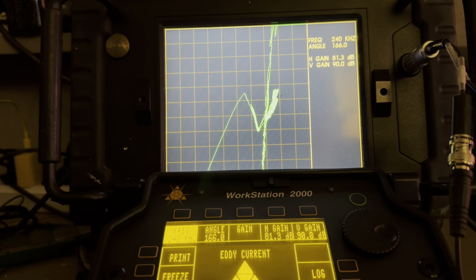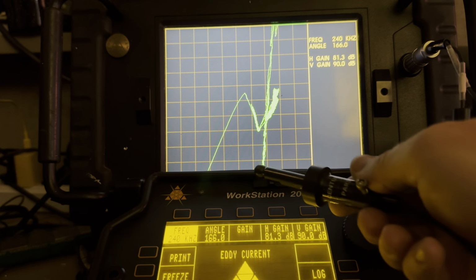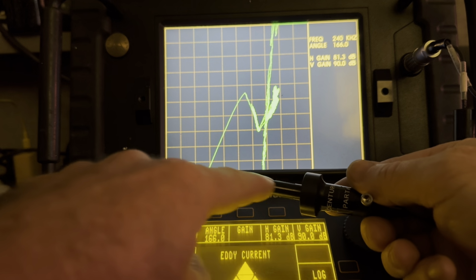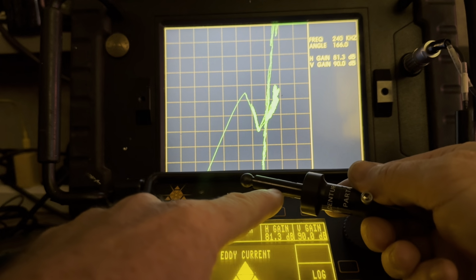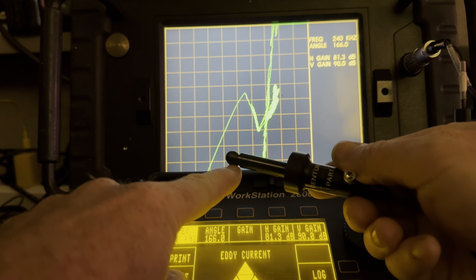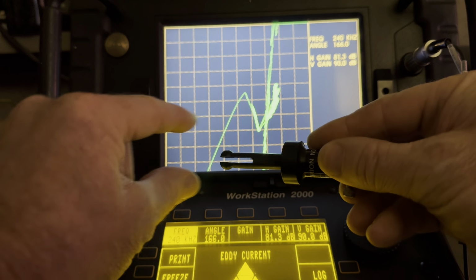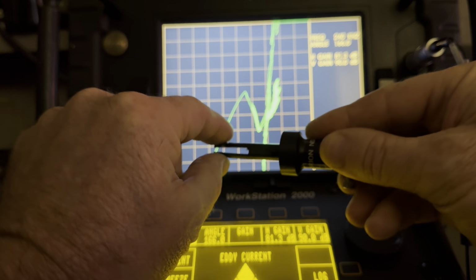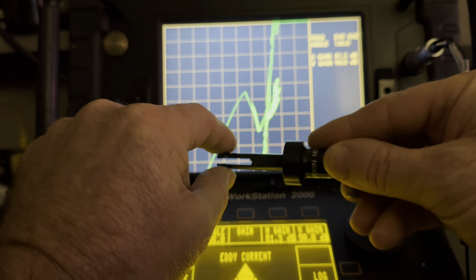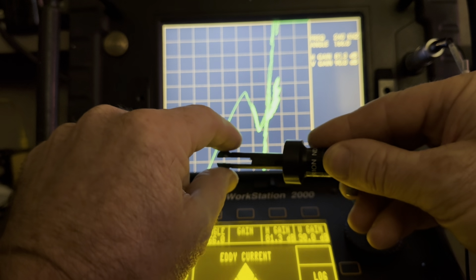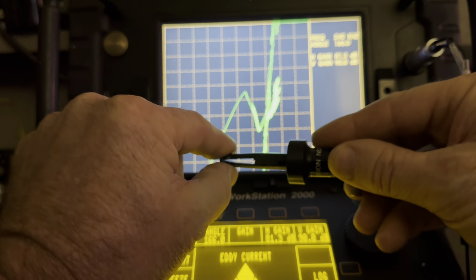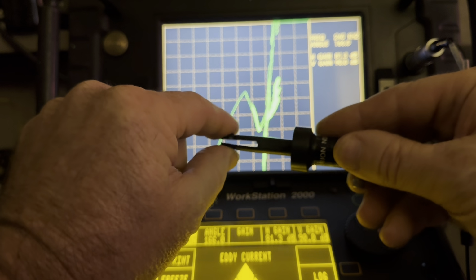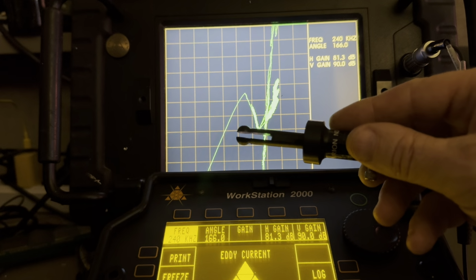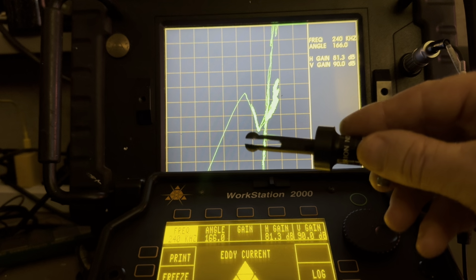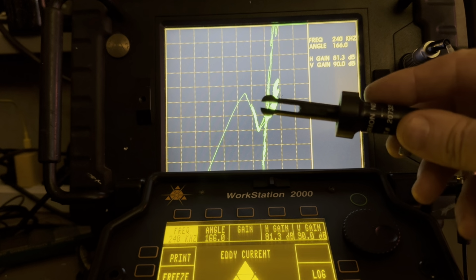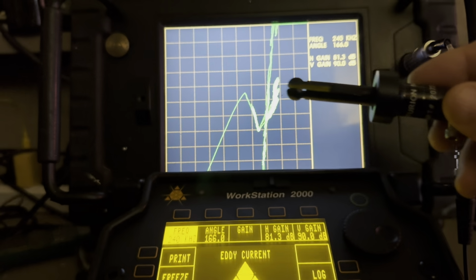First thing, we got to see if the probe's active. On this particular probe, you can see there's a white line that runs down it this way - that indicates where the coil is, right there. So I'm turning that line downward. You see the space in here? That's to provide some spring action so the coil will hopefully stay surface riding inside of the hole. If you use too small of a probe, or if the spring action's gone, you may have liftoff, and that's going to give you unnecessary noise, and it's also going to challenge your detection of flaws. So you want to have the right probe size, make sure that it's in nice working order.